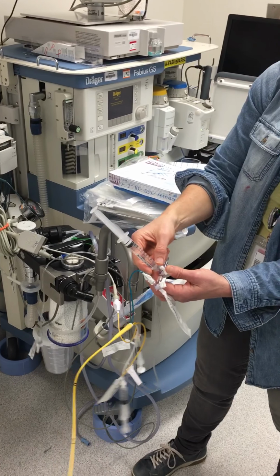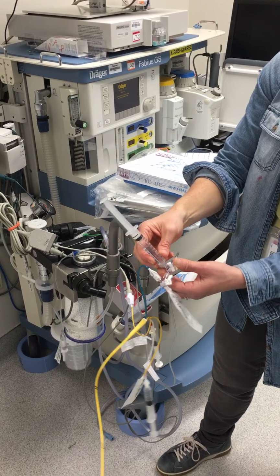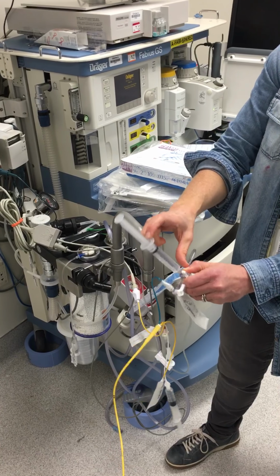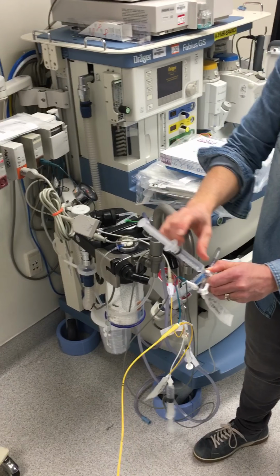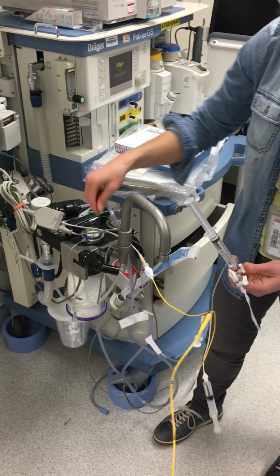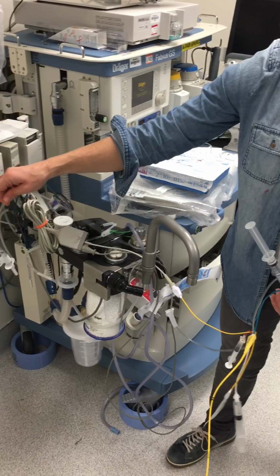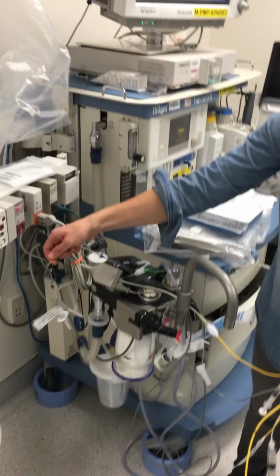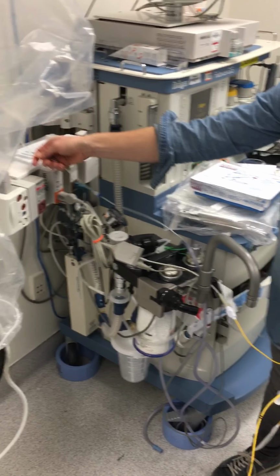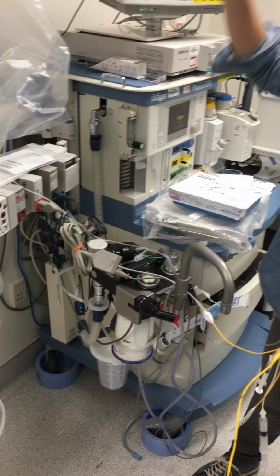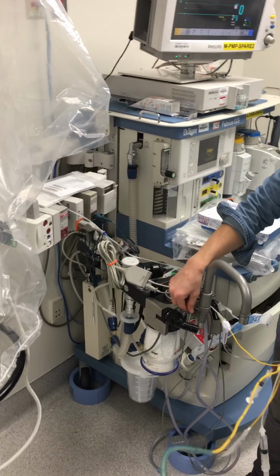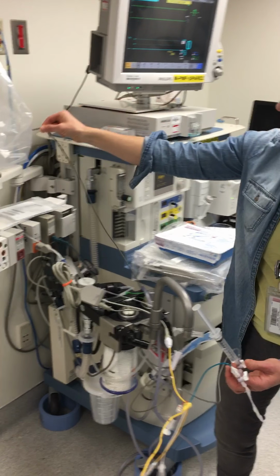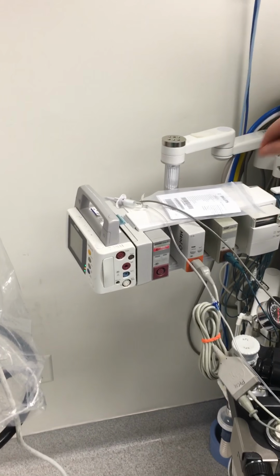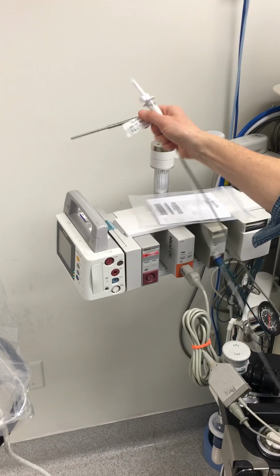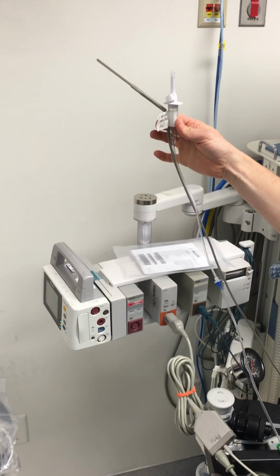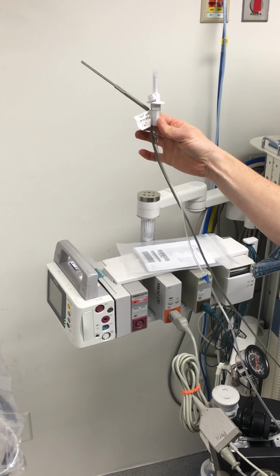And the reason why I'm saying that is because you're going to draw up fluid from the bag here, and you're going to make sure there's no air in it before you inject, for sure. But this could be in a bag at a level, it doesn't have to be above the patient's heart or hung up on an IV pole. It really can't be, because it has to be in the ice bath. This is going to be in the ice bath, because essentially this is measuring the temperature of the injectate.